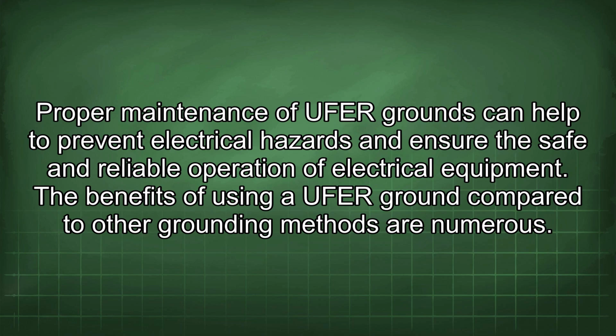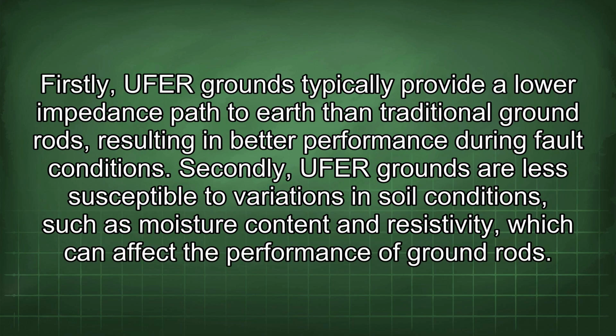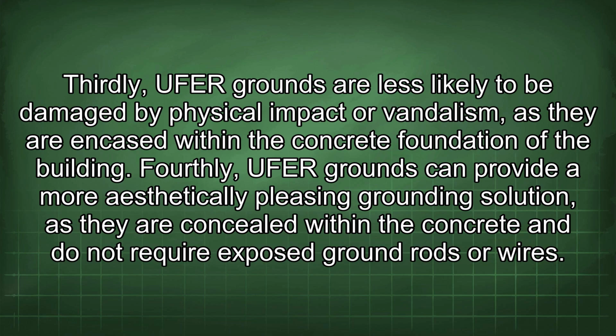The benefits of using a UFER ground compared to other grounding methods are numerous. Firstly, UFER grounds typically provide a lower impedance path to earth than traditional ground rods, resulting in better performance during fault conditions. Secondly, UFER grounds are less susceptible to variations in soil conditions such as moisture content and resistivity, which can affect the performance of ground rods. Thirdly, UFER grounds are less likely to be damaged by physical impact or vandalism, as they are encased within the concrete foundation of the building.